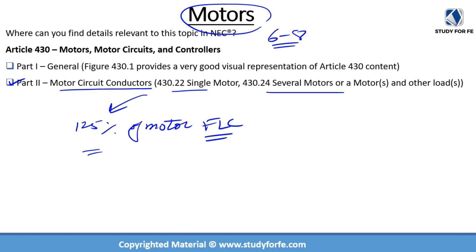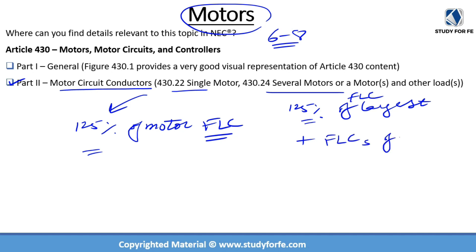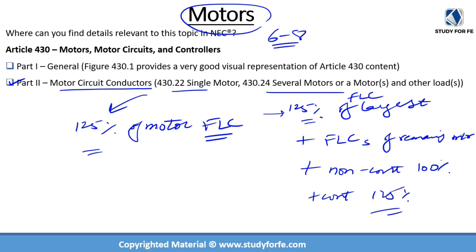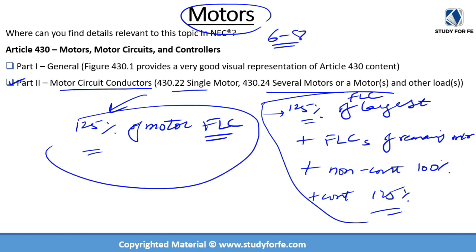Motor FLC — motor full load current — is very important and will come up several times in this lecture. When dealing with several motors, you apply 125% of the FLC of the largest motor, plus the FLCs of the remaining motors. If you have a combination of motors and other loads, you still apply 125% of the largest motor FLC plus the remaining motor FLCs, then add 100% of non-continuous load ratings and 125% of continuous load ratings. This is how we size conductors — it's something you will encounter quite often as a power systems engineer.